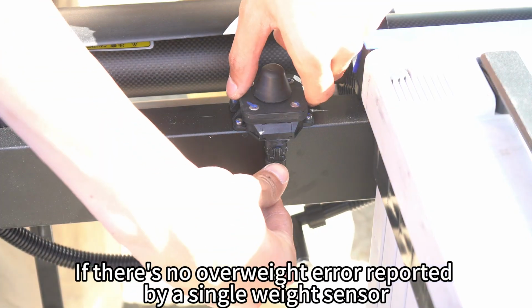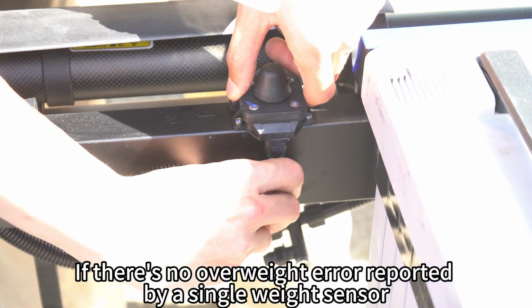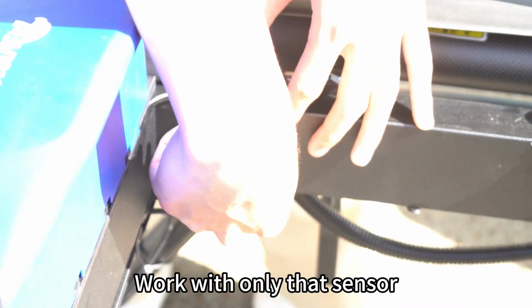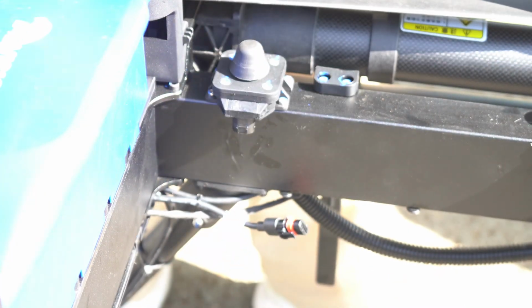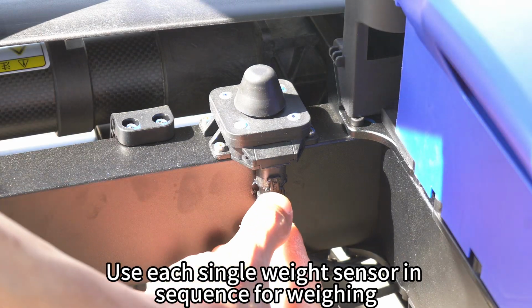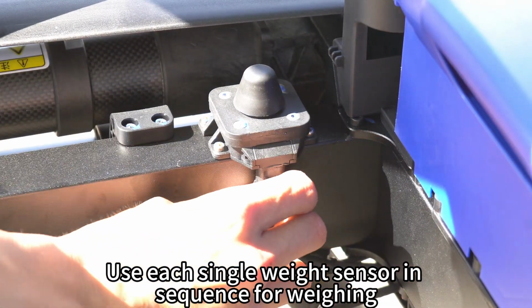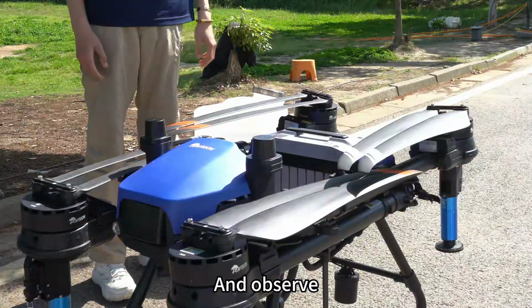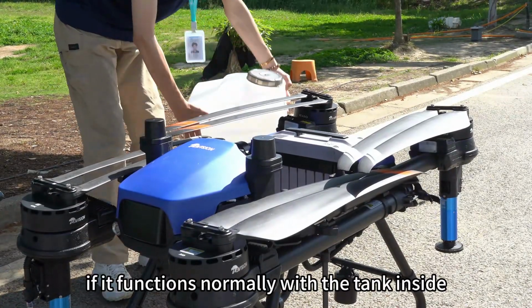If there's no overweight error reported by a single weight sensor, work with only that sensor. Use each single weight sensor in sequence for weighing, and observe if it functions normally with the tank inside.